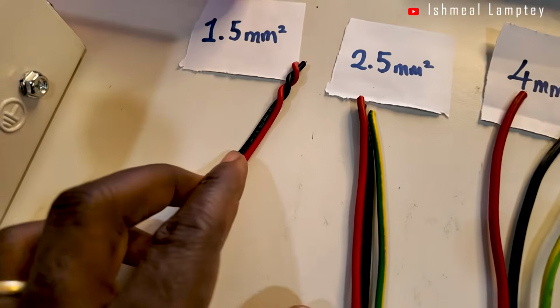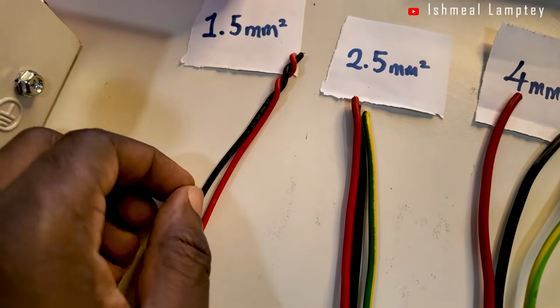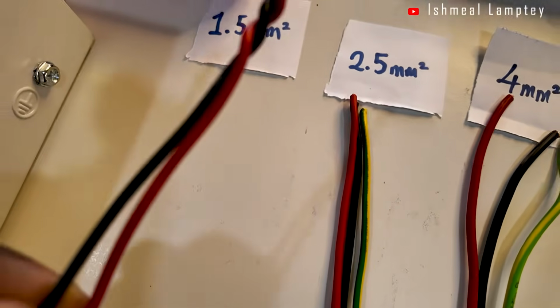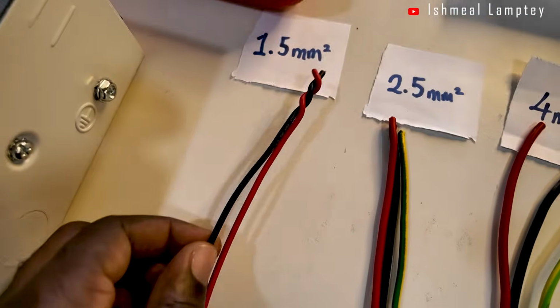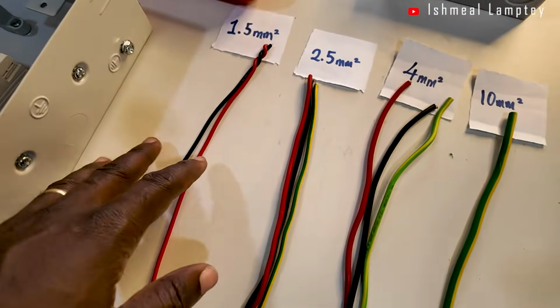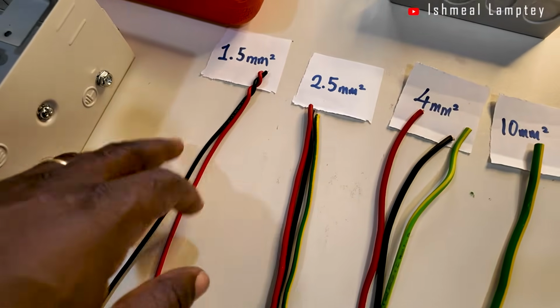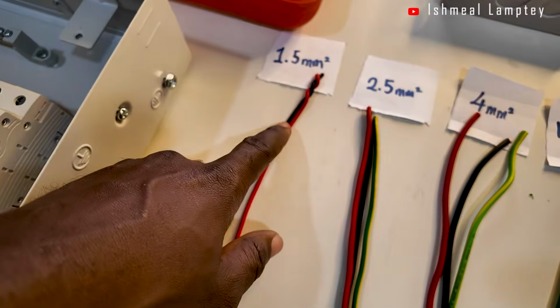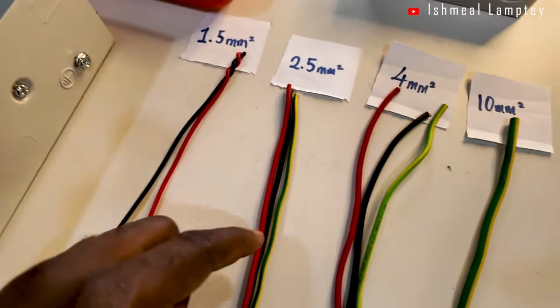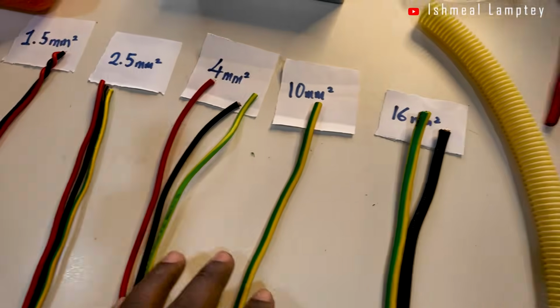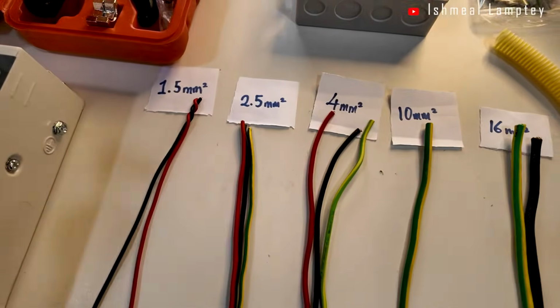One way you can tell the size of a cable is to read it. If you look closely, there are small inscriptions on it. I'm sure you might struggle to see it on camera, but if you read the ratings, numbers or letters written on it, you'll be able to tell that this has 1.5 mm square written on it, this has 2.5, this has 4 mm, 10 mm, 16 mm, among others.